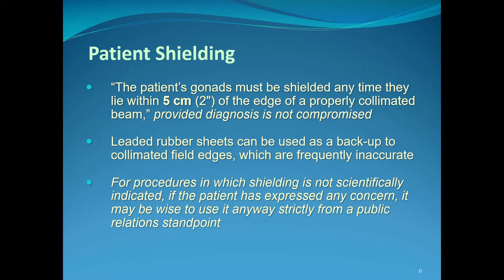Leaded rubber sheets can be used as a backup to collimated field edges, which are frequently inaccurate. A good example is using leaded rubber sheets at the posterior aspect of the patient for lateral thoracic or lateral lumbar spine images, because that extra thick body tends to scatter a lot of x-rays and leads to fogging on the image. Placing a leaded rubber sheet right at the edge of the collimated field can clean up the images. Leaded rubber sheets don't lower patient exposure since they're placed on the tabletop or image receptor, but they do improve image quality. To be clear, leaded rubber sheets are not a type of patient shielding.